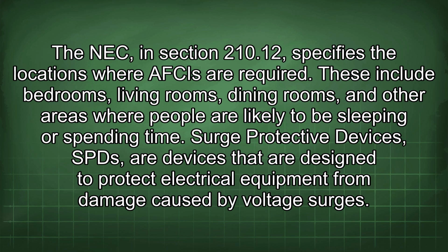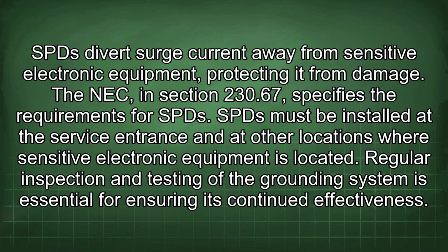Surge protective devices, SPDs, are devices that are designed to protect electrical equipment from damage caused by voltage surges. SPDs divert surge current away from sensitive electronic equipment, protecting it from damage. The NEC in section 230.67 specifies the requirements for SPDs. SPDs must be installed at the service entrance and at other locations where sensitive electronic equipment is located.